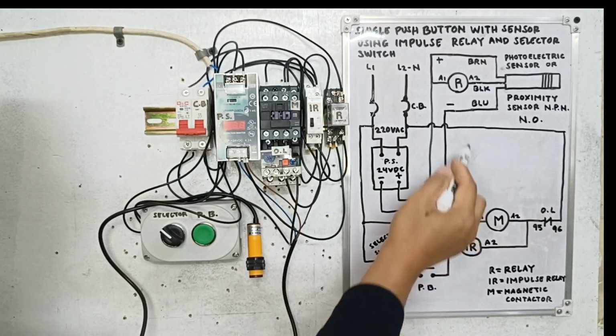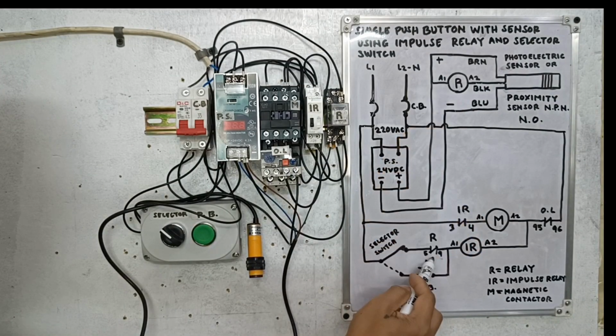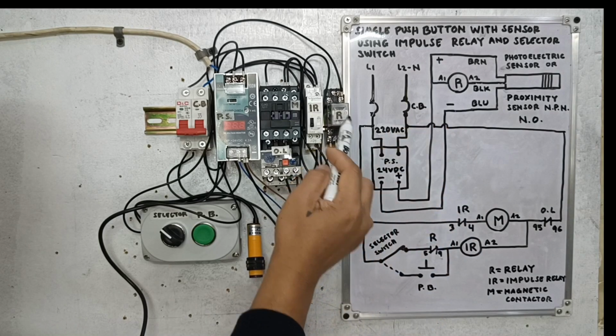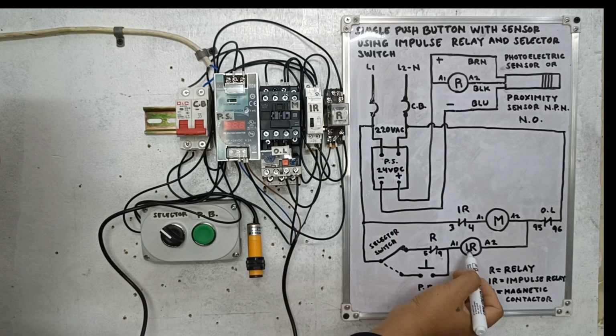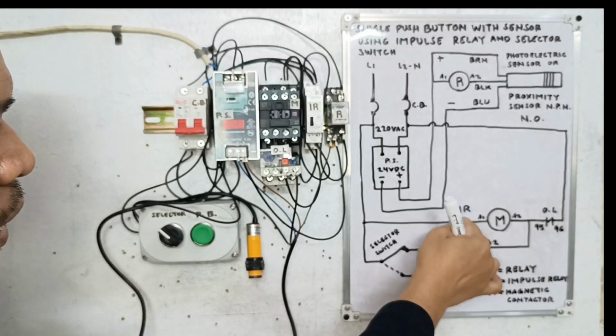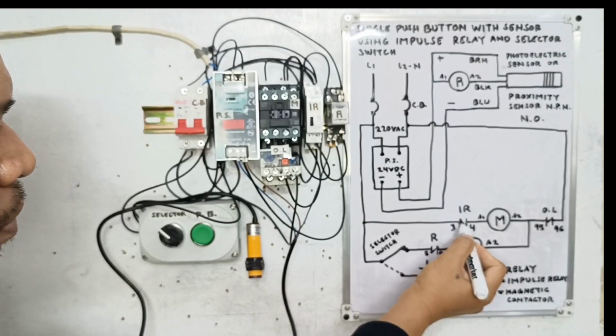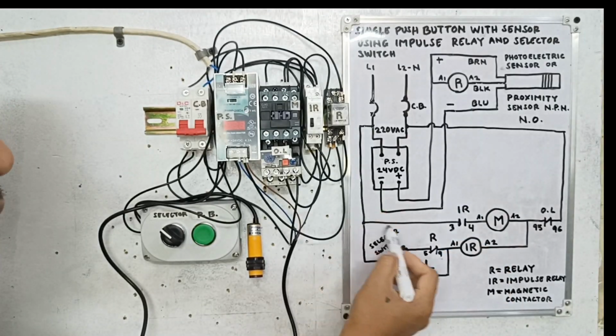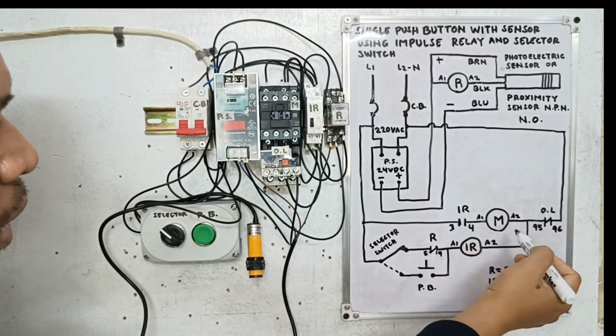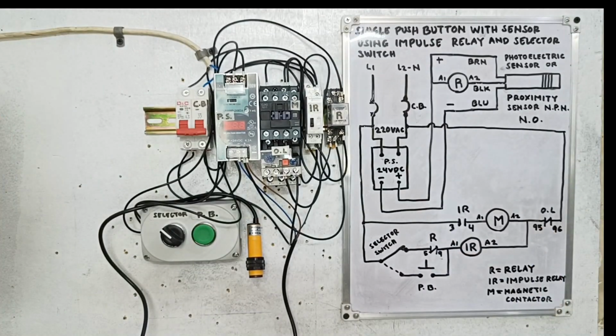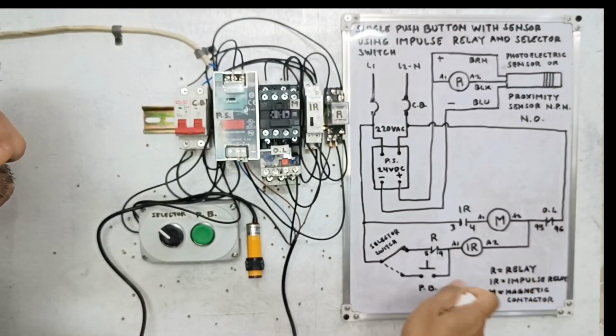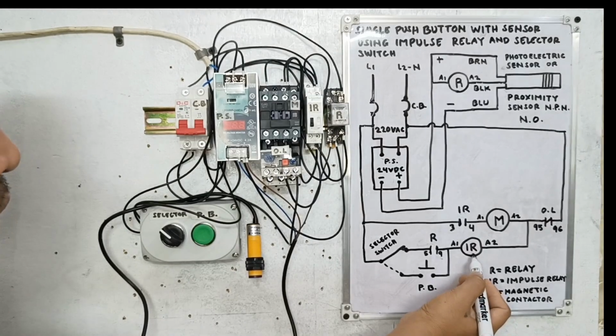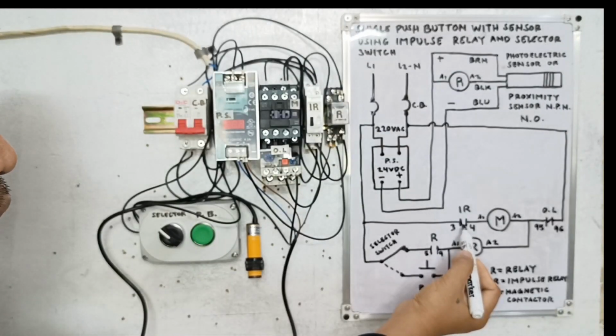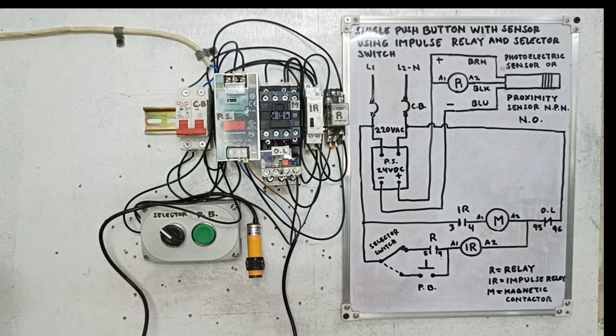After this contact closes, because the relay will activate, this is the normally open contact of our relay. So the impulse relay activates again, and this one will trip for the impulse relay. Now the contact will open, the current stops until here, and the magnetic contactor will also be off. Now, if the sensor cannot sense the object, this one will open. The impulse relay will cut off the power. Still, this contact will be open. Just like that, the position.